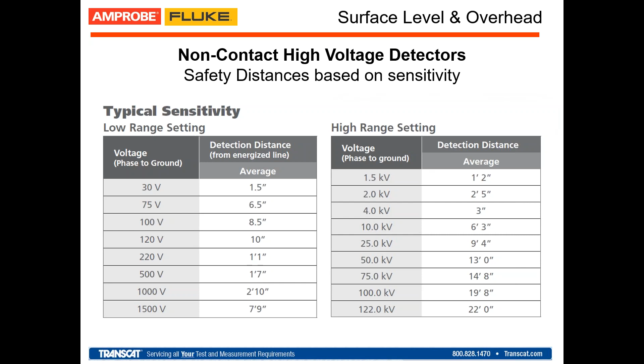Another thing is that NCVs as a technology are typically between 10 to 15 inches long, but they come with adaptable hot sticks, right? Or they come with adapters so that a hot stick can be attached. So if you want to stay as far as possible from the detection distance, even if you're within the thresholds defined by the sensitivity table, you can just use a hot stick and stay way, way far from the hot areas.